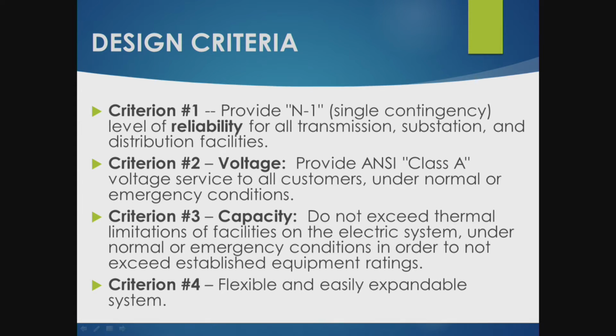We also keep track of the thermal capacity of the electrical equipment — how heavily equipment is being loaded, and whether there are any red flags for overheating, for example transformers rated for a certain KVA power usage. Conductors and underground cable all have certain capacities. If you exceed the recommended capacity, there will either be an equipment failure or a loss of expected life on that equipment.